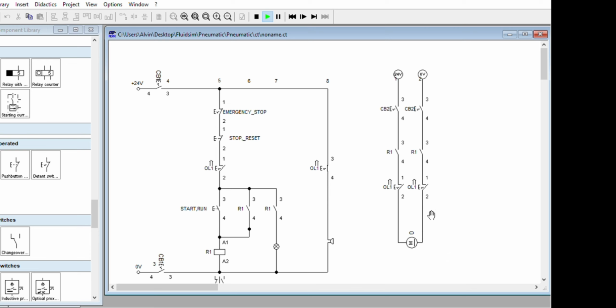See what causes the overcurrent. That is not a short circuit for sure. Ground fault, mechanical trouble, bearing, winding troubles, whatever causes that. So you need some skills here to test the motor, including the insulation, whatever causes the overload or overcurrent. Let's say overloading at the mechanical side of the motor. Then that's the time you are going to reset this. You are going to review your setting based on the motor's current. Check the quality of the power contacts. Maybe one is not properly in contact. You have single phasing if you have three phase. So turn off the circuit.